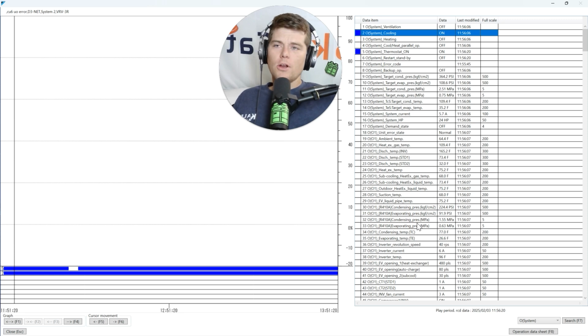So when we talk about cooling mode, I like to go back to the 3 pillars. What's the first pillar in the 3 pillars? Say it with me: suction superheat. I like to follow the path of compression. In heating mode, I follow discharge superheat first, on the leaving side of the compressor. But in cooling mode, I like to look at the beginning part, right before the compressor. So we're talking about suction gas coming back down the suction line to your actual inverter compressor.